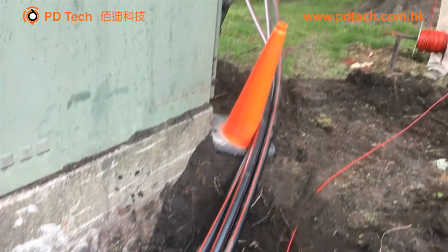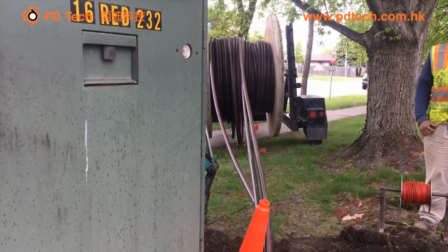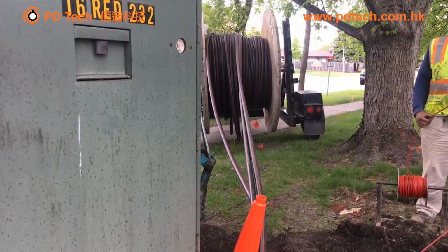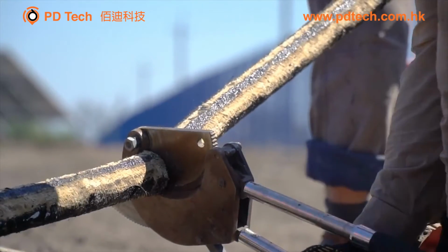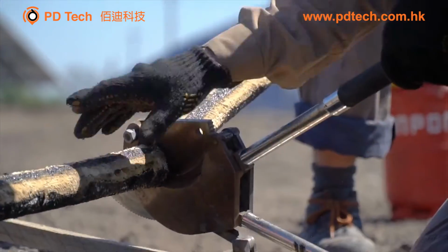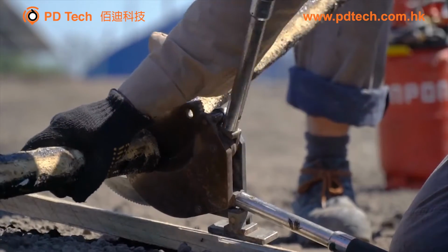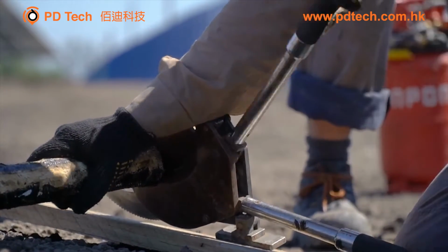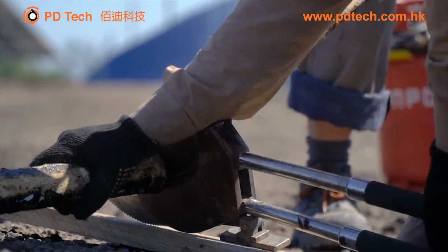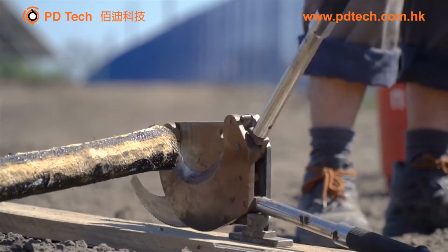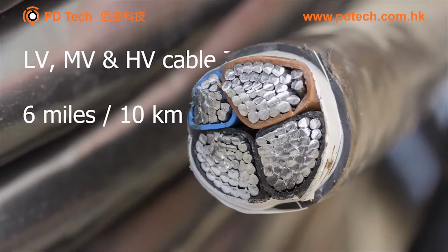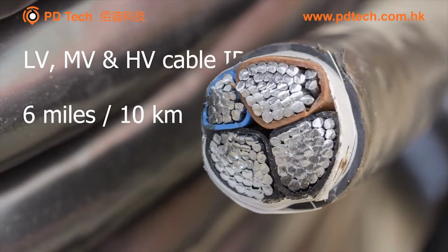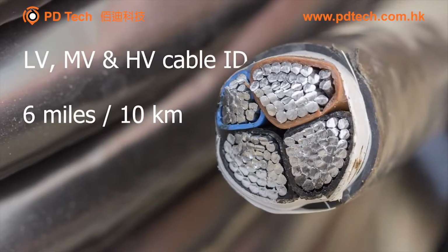When cable systems are replaced and older cable systems are removed from the power distribution network, they must be positively identified prior to removal. Even when tagging is available, how can we be sure it's accurate? The VCI-3 system is designed to clearly identify three-phase, low, medium, or high voltage cables, typically up to 6 miles or 10 kilometers, and often more.